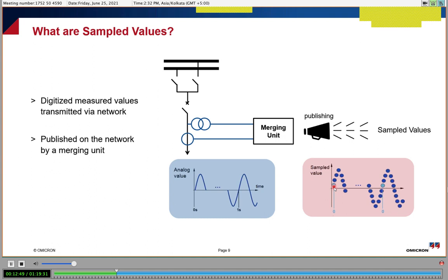And for power quality, where we have to see the interharmonics, voltage dips and swells, they define even more, 256 samples per cycle. That was done in around 2004 when the implementation guideline came, this 9-2 Light Edition. Currently, we even have IEC 61869-9, which I will discuss more during the practical and afterwards also.